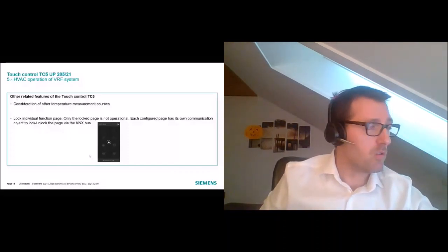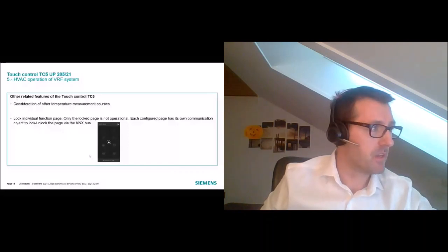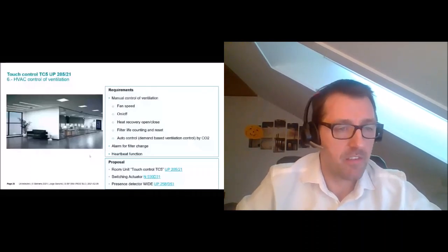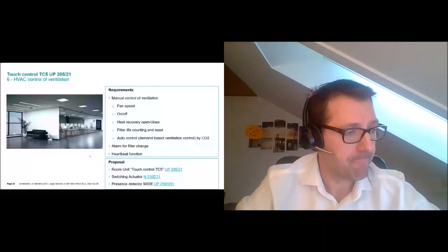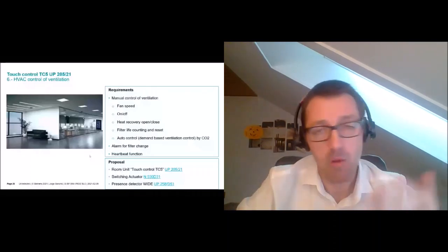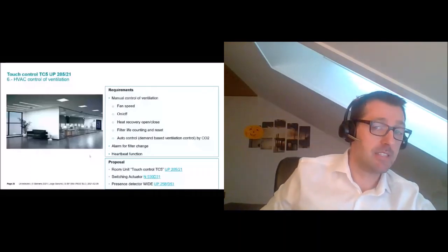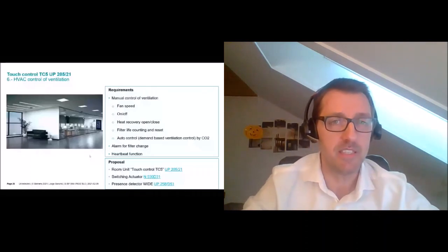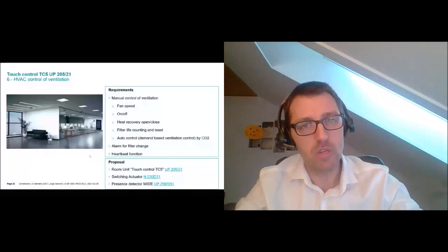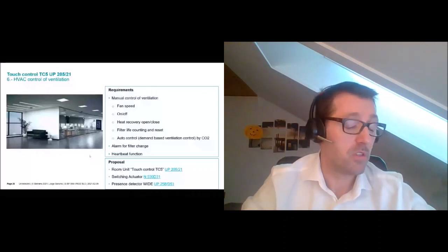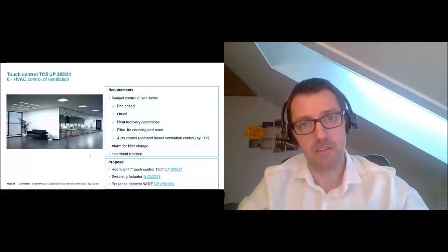Use Case 4: ventilation control. The requirements are fan on/off, heat recovery, filter life counting, and control based on CO2 level. The customer also wants an alarm to know when to change the filter, and a heartbeat function. Proposal: TC5, switching actuators, and a presence detector Wide. For ventilation, as with VRF, we have a dedicated page — when you select ventilation in the TC5 ETS settings, it automatically generates a page with the CO2 value display, modes, heat recovery switch, and all the controls you need.